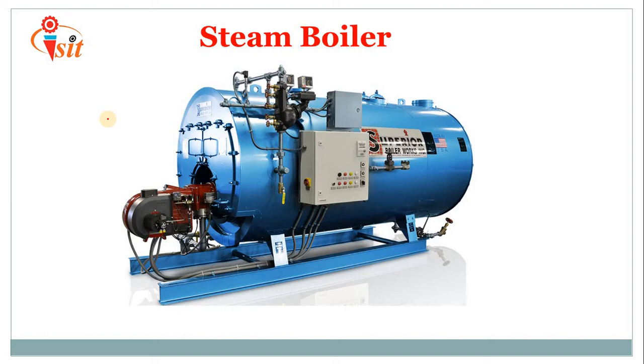As far as mountings are concerned, take the example of safety valves, water level indicators, and pressure gauges. Then there are different kinds of analyzers and the fusible plug. These all come under boiler mountings. These are the most essential. Without them we never operate the steam power plant, as far as the safety point is concerned and IBR norms are to be considered.